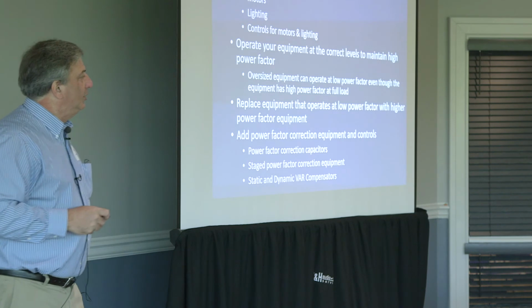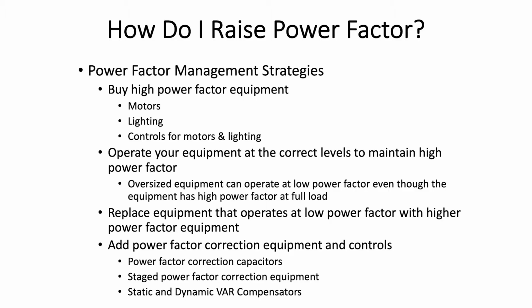So that becomes important in terms of what we're going to do there. So how do I raise power factor? I buy high power factor equipment. How many of you have ever done a spec when you sent a piece of equipment to purchasing that said the power factor must be above 80% for this 100 horsepower motor we're buying? I see one hand. Yeah, we've done that. I'm starting to see more and more companies now put a power factor spec into purchasing to say, if it doesn't meet this number, we don't want it in our plant. That type of thing. So people are attacking it that way.